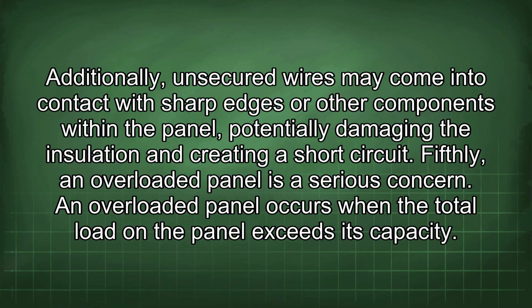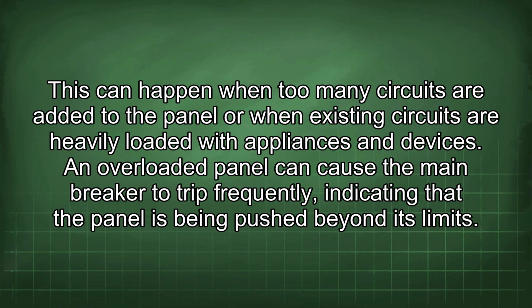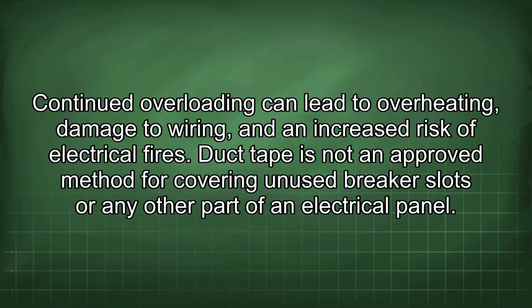Fifthly, an overloaded panel is a serious concern. An overloaded panel occurs when the total load in the panel exceeds its capacity. This can happen when too many circuits are added to the panel or when existing circuits are heavily loaded with appliances and devices. An overloaded panel can cause the main breaker to trip frequently, indicating that the panel is being pushed beyond its limits. Continued overloading can lead to overheating, damage to wiring, and an increased risk of electrical fires.